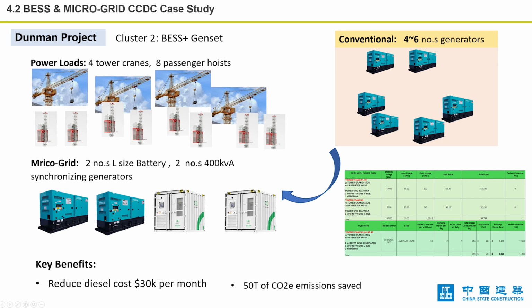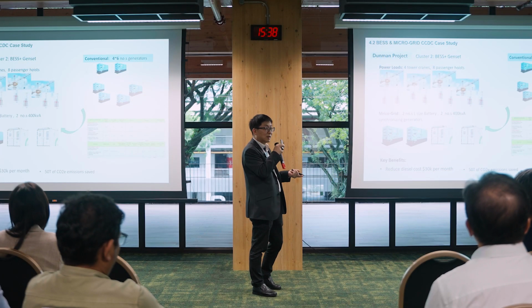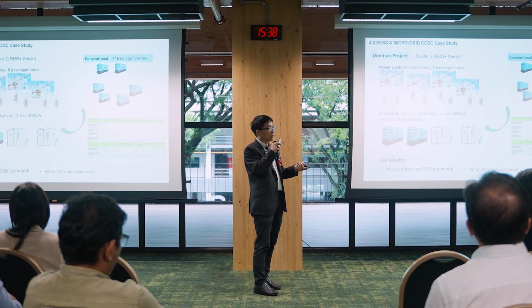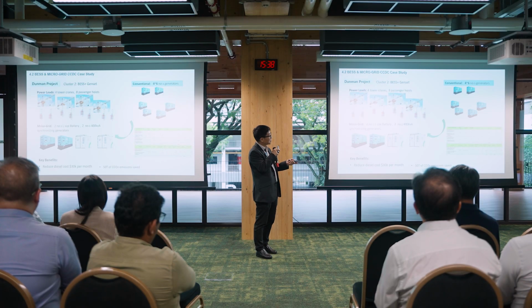With these micro grids, we only use 2 L-size batteries plus 2 units of 400 kVA synchronized generators, which can solve all the power demand on site for these 4 tower cranes. After running a few months, we estimate cost savings of about 30K per month in diesel, equivalent to about 20,000 liters per month, and also equivalent to 50 tons of CO2 emission reductions.